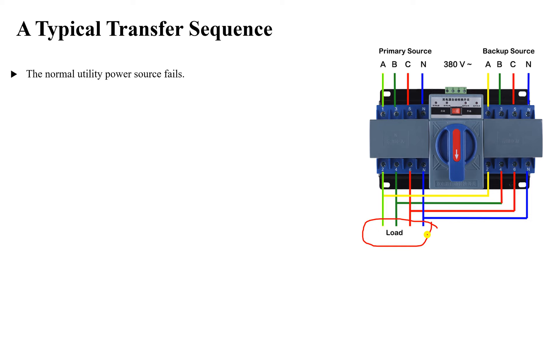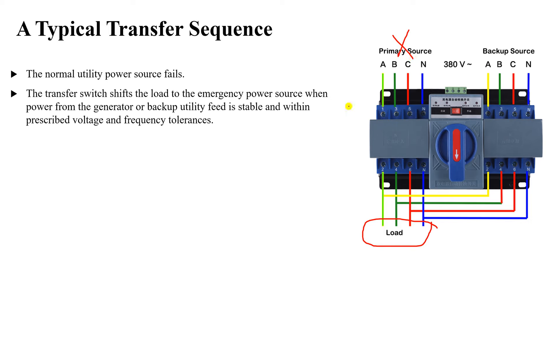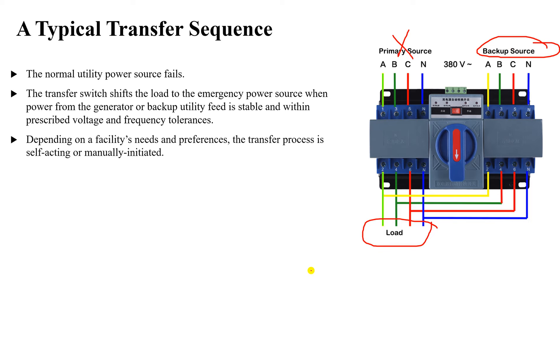Here is the operating sequence of the transfer switch. If the normal utility power source fails — if there is a problem with the primary source — the transfer switch will stop taking power from the primary source and start providing power from the backup source. The transfer switch shifts the load to the emergency power source when the backup generator or utility feed is stable and within the prescribed voltage and frequency tolerance.